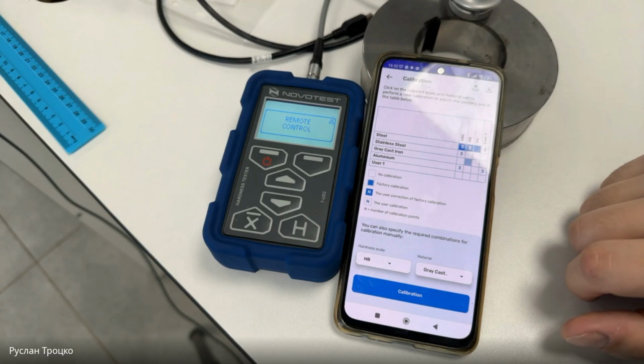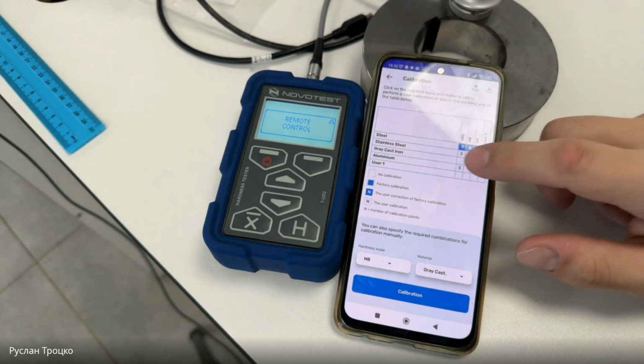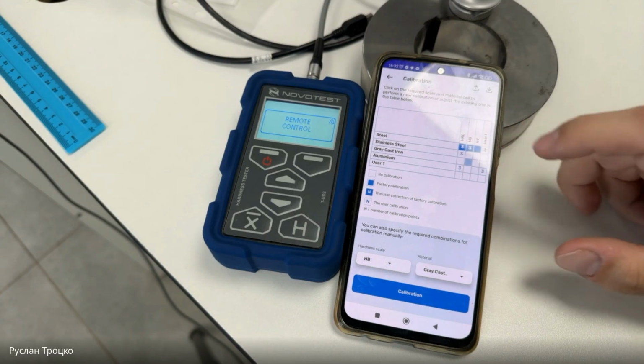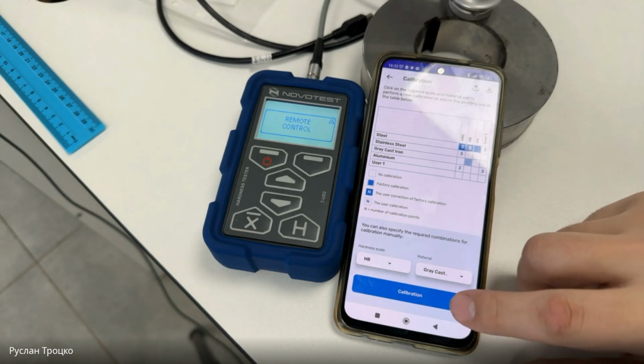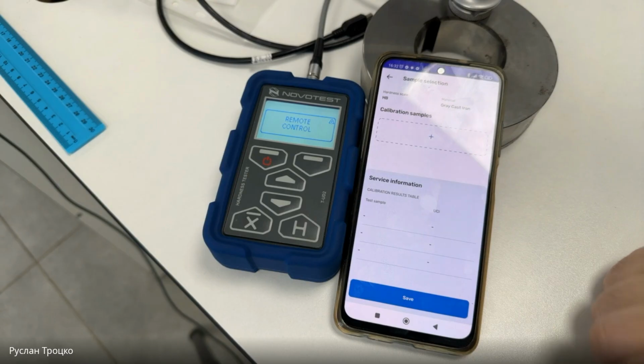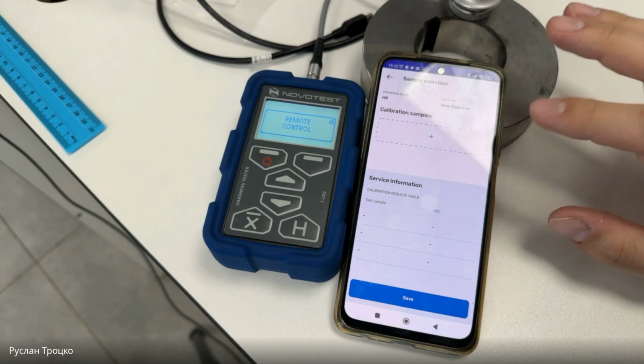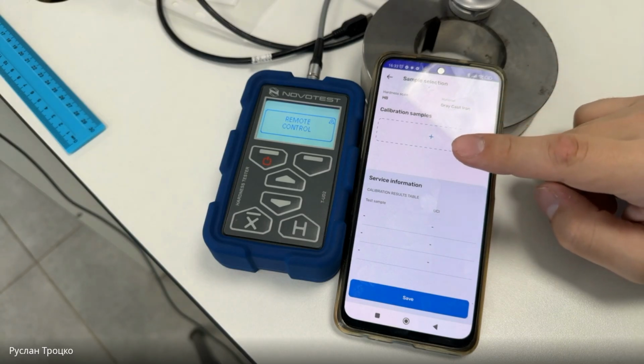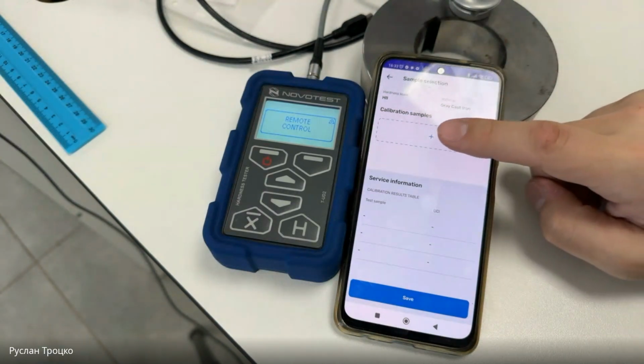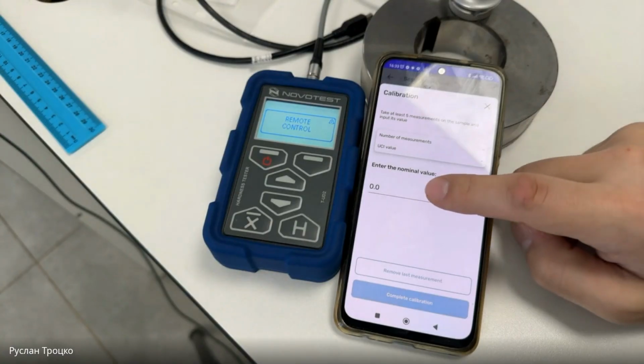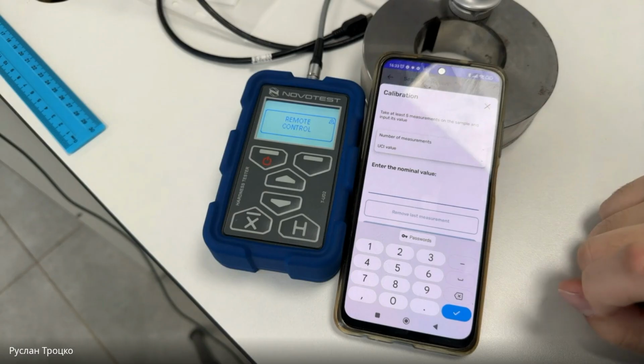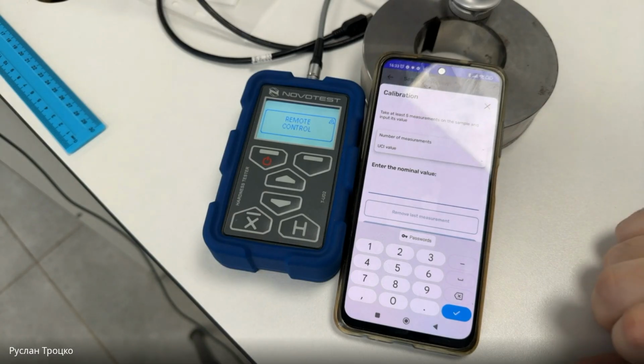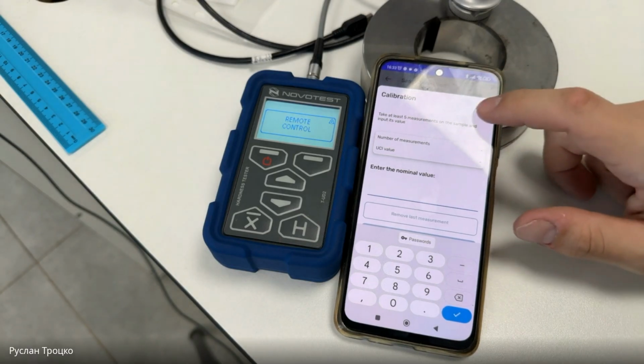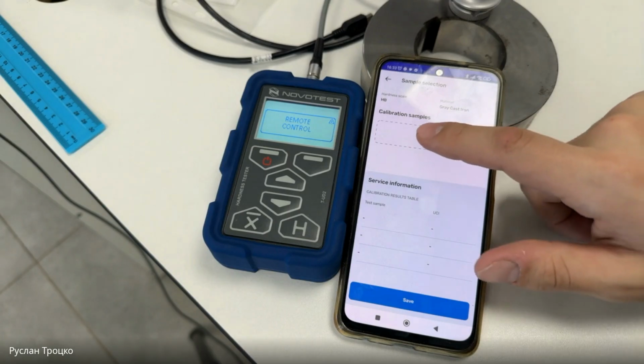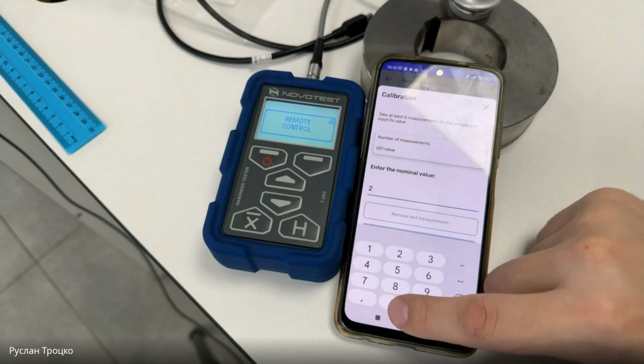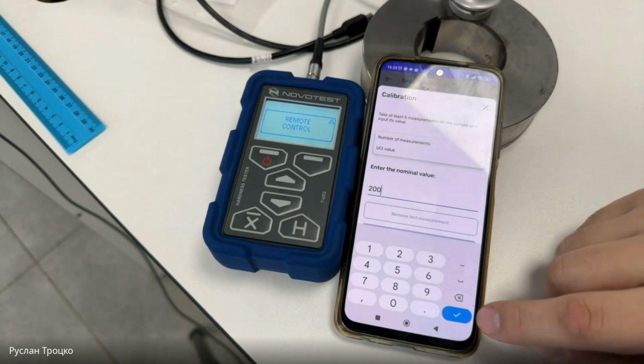Let's create a new calibration. I click here, and I press calibration. Okay, now I have to do 5 measurements, and I choose my calibration samples. This is my first calibration sample. I add it. I enter the nominal value. For example, my first calibration sample is, okay, this is HB scale. Let it be 200 HB Brinell.